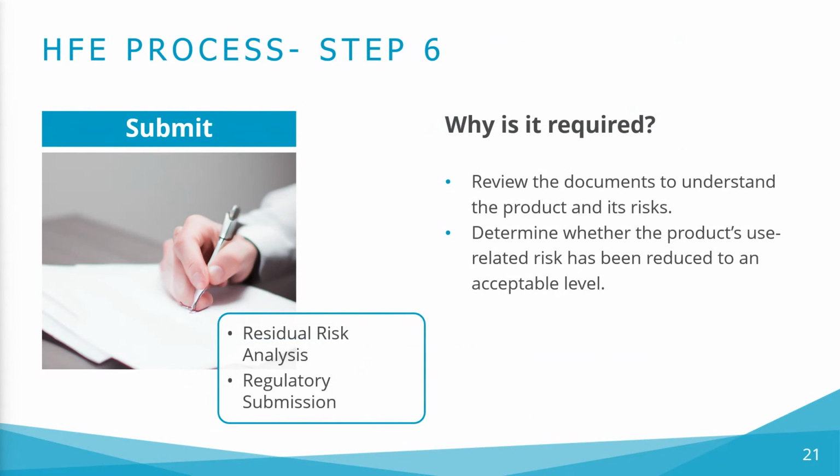HFE process step 6, submit. During the submit step, manufacturers must perform their final HFE analysis, residual risk analysis, to confirm they have reduced use related risk to an acceptable level and that the product design is final.